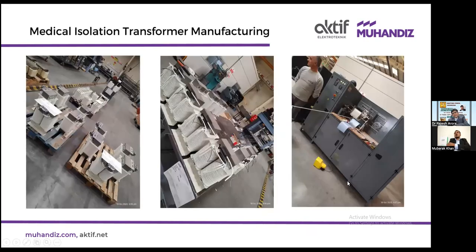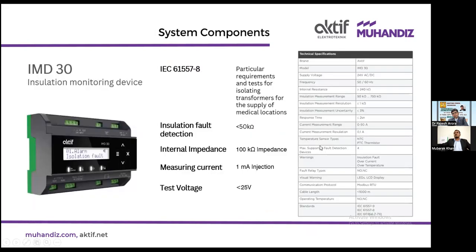This is a medical isolation transformer being manufactured in our factory. As you can see, we do the complete assembly, winding, and everything. Now, coming to the insulation monitoring device, it is recommended as per IEC 61557-8. The same details are mentioned in the NEC standard, which also emphasizes that it should be compliant to IEC 61557-8. The main requirement is that it should be able to detect if the insulation resistance value of the phase conductor with respect to ground goes below 50 kilo ohm.